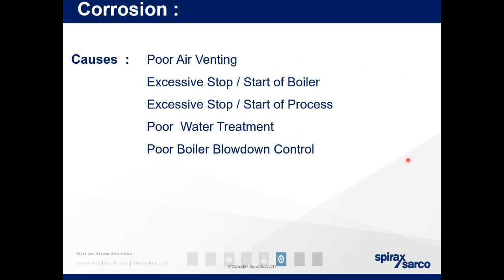Excessive stop-start of the boiler. Again, referring to the question we just had about on-off control with water. This could be on your boiler. It will be running harder when it has a thermal shock, so a cold water load added to it. So it's burning more fuel. That means you have peaks and troughs when it comes to your steam production. Excessive stop-start of process is a similar thing. All our processes on all our sites will run and stop for a period of time, but what this is talking about is doing that several times in an hour, and that's going to give you excess wear.